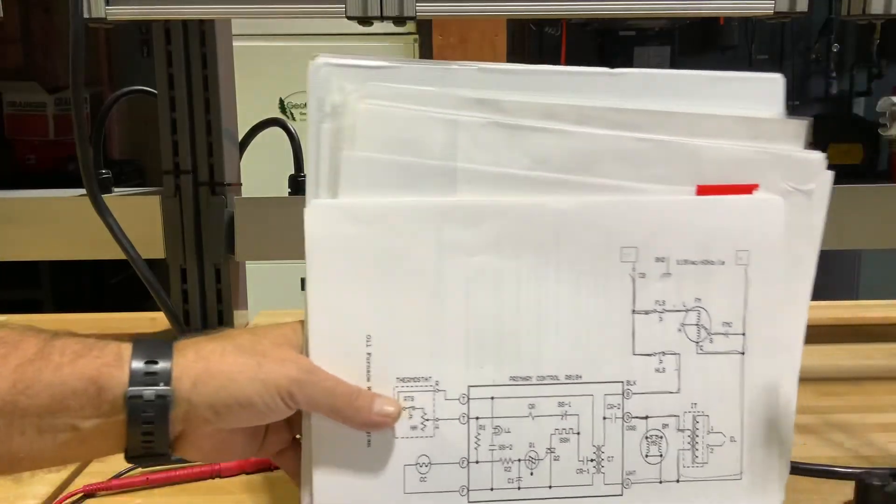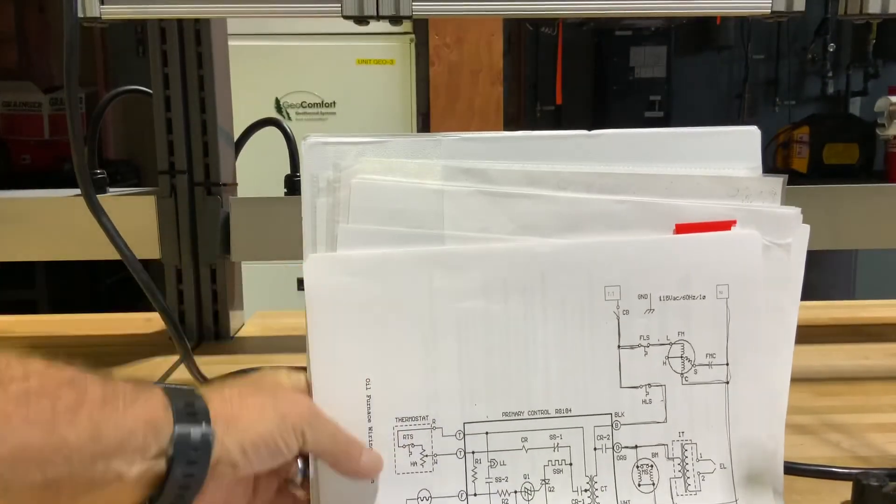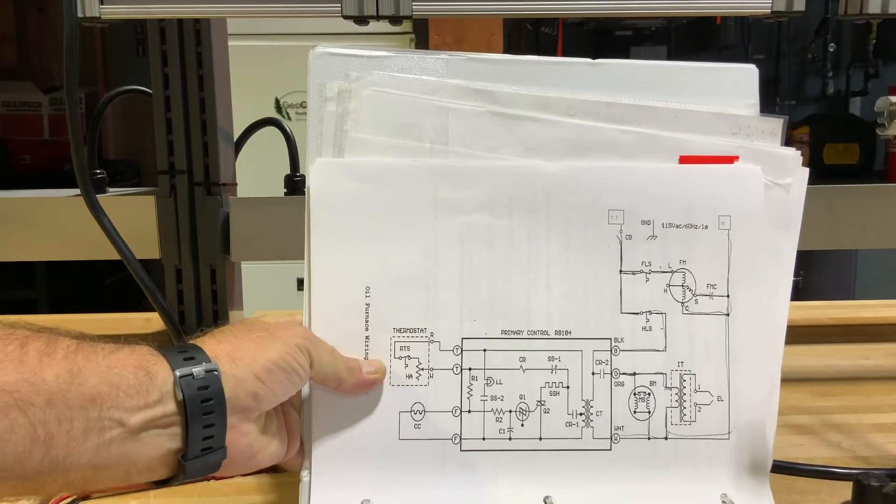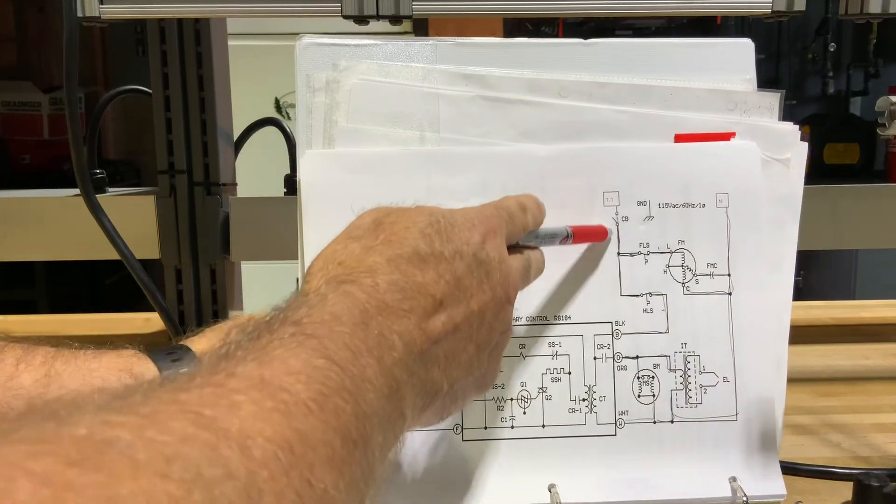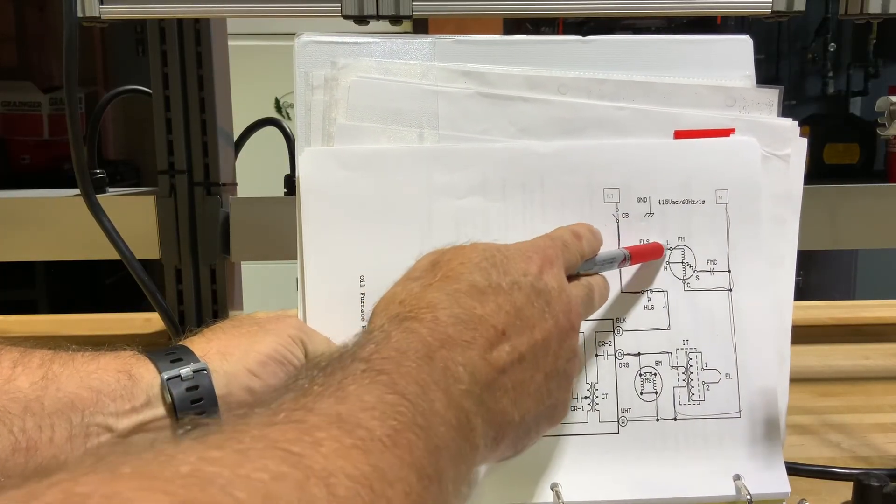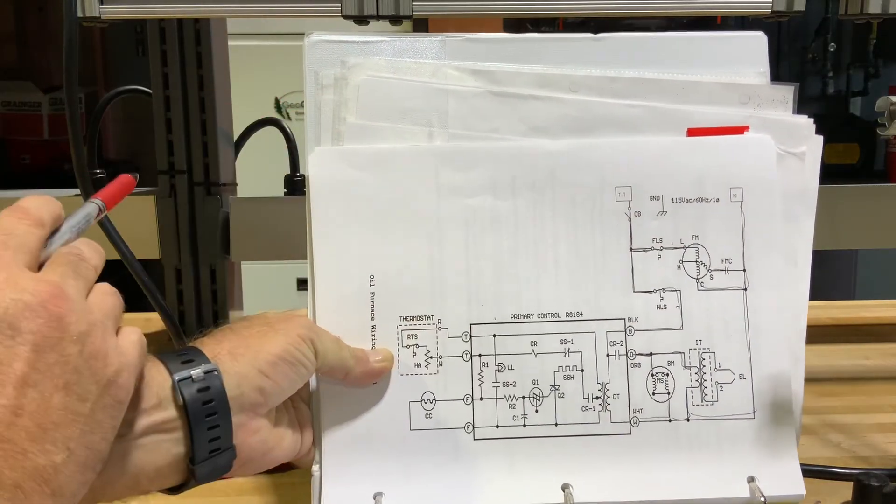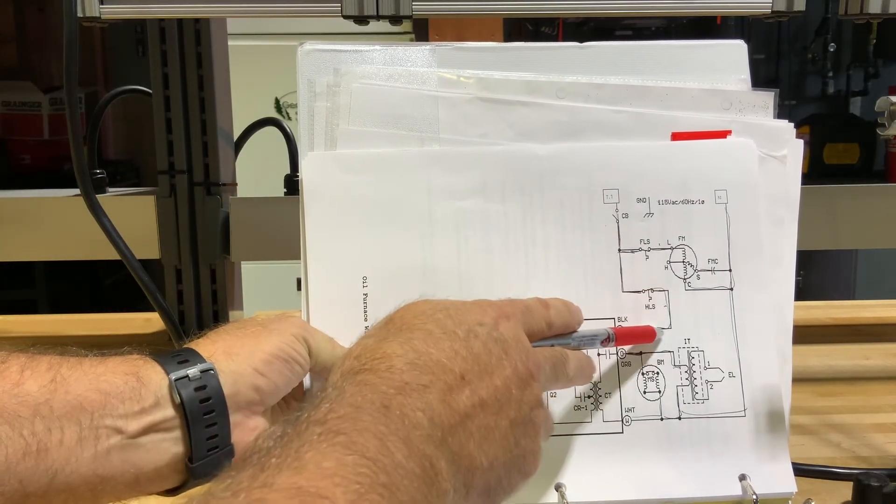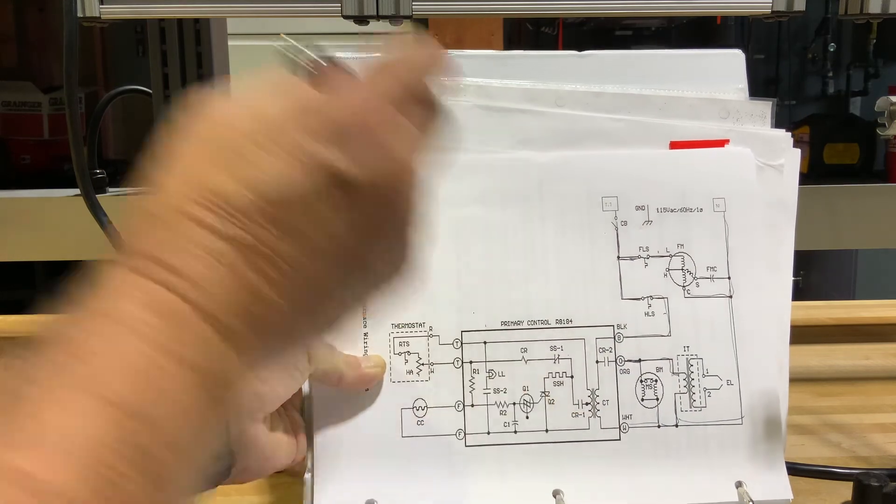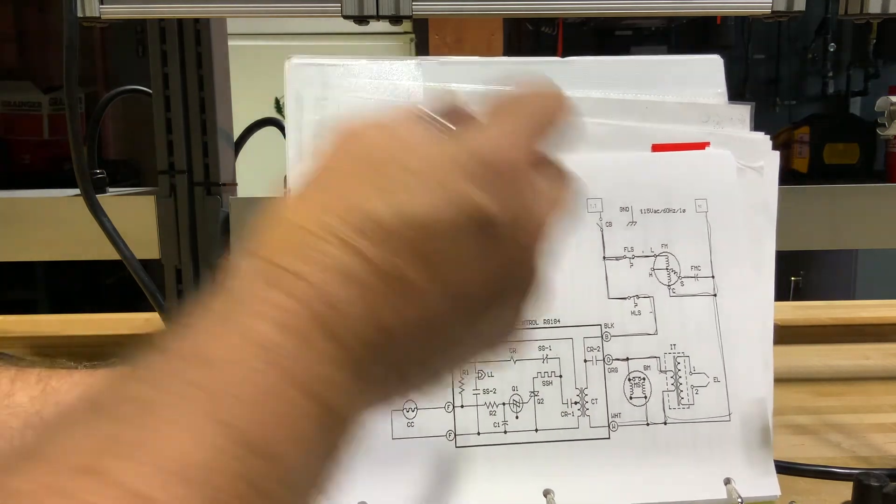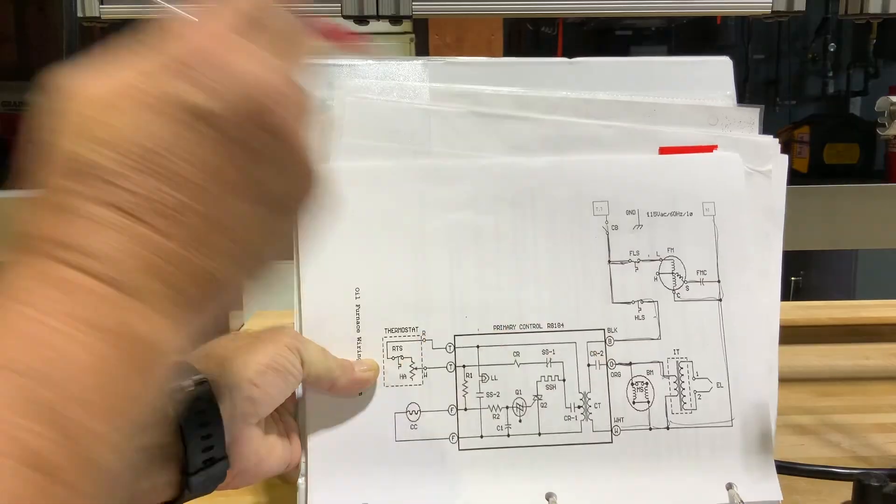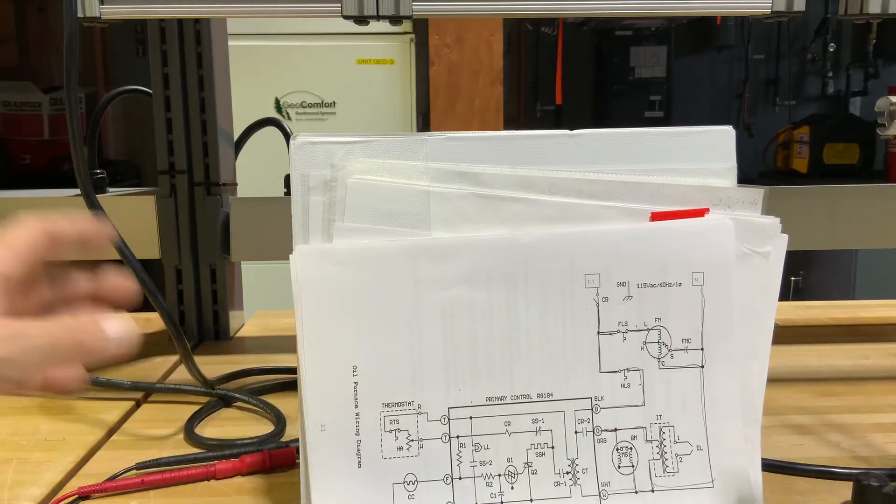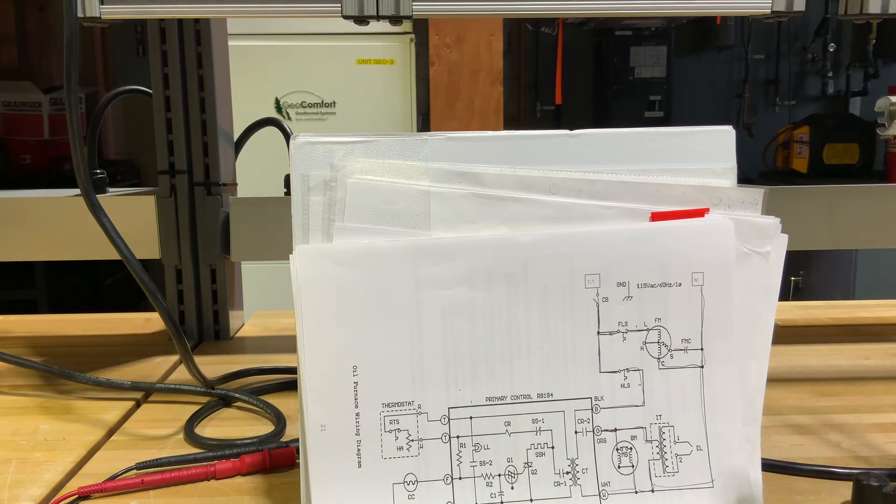If we look at this wiring schematic, we can see here's our incoming power, here's our fan switch going to our fan motor, here's our limit switch. Now this is your black wire - that black wire is going to our primary control. So if this opens, we kill all power to our primary control. That shuts everything down. So that's kind of how that fan limit switch works.